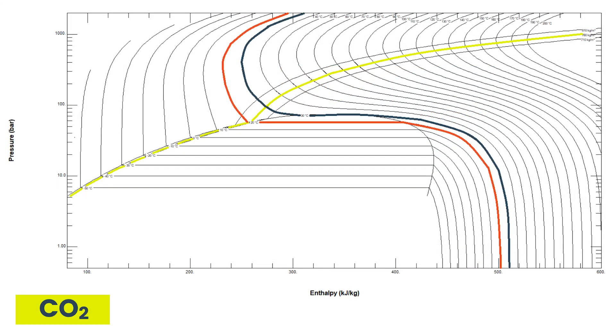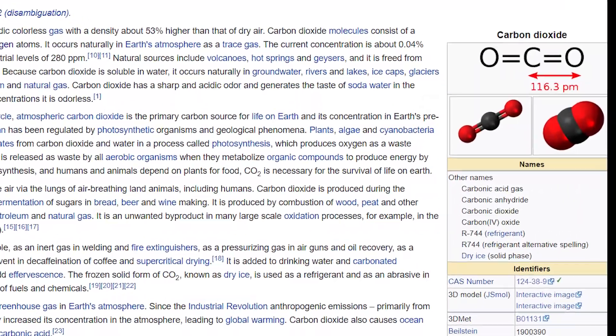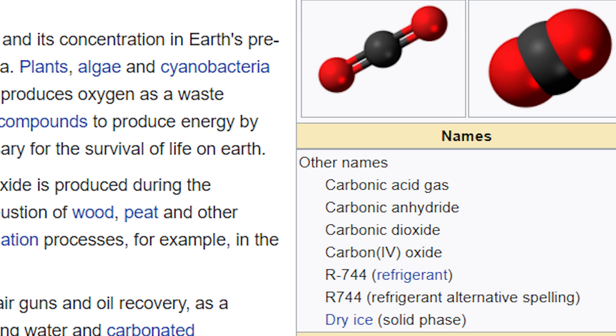That is why we have no data for carbon dioxide below 5 bar, and that is also your first reason why you would not want to use carbon dioxide as a refrigerant in your own house. Now let's make it very clear: carbon dioxide is a refrigerant. It has its own R number like most refrigerants do, and it is used in industrial applications as a refrigerant. The trouble is that you have to maintain higher pressures. If ever the pressure in your system drops below the triple point pressure and the system is cold, you will form solid carbon dioxide that's a pain to remove.